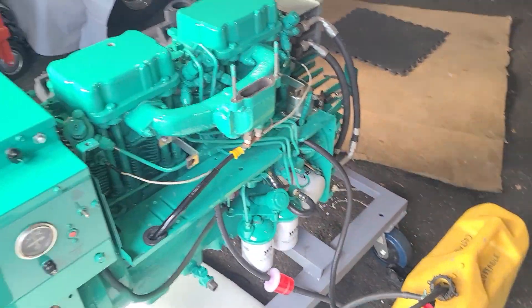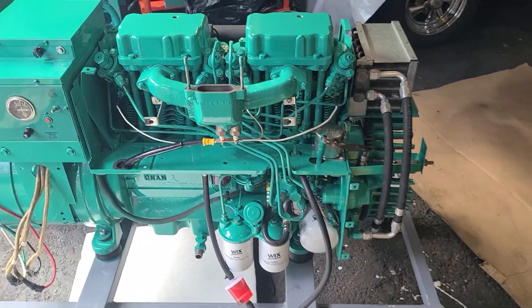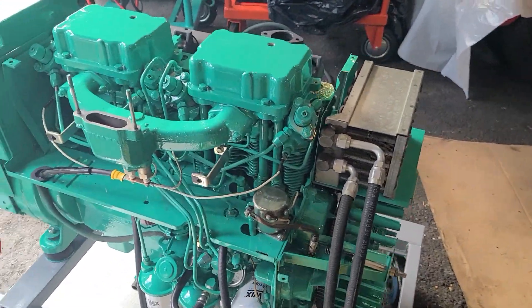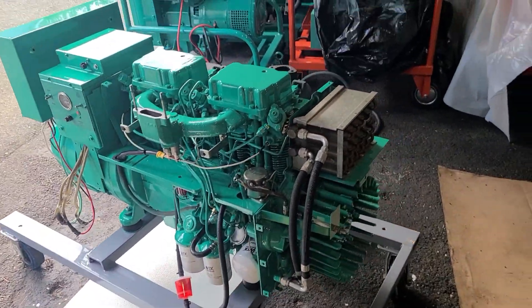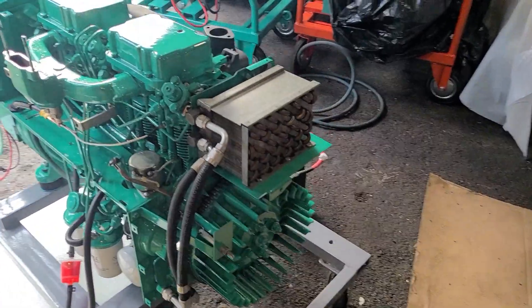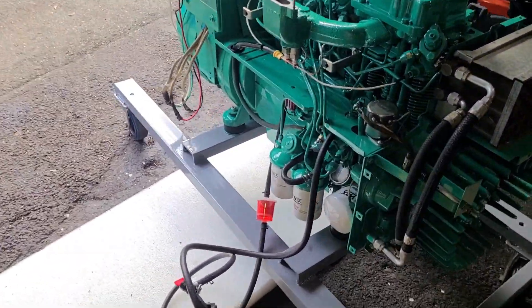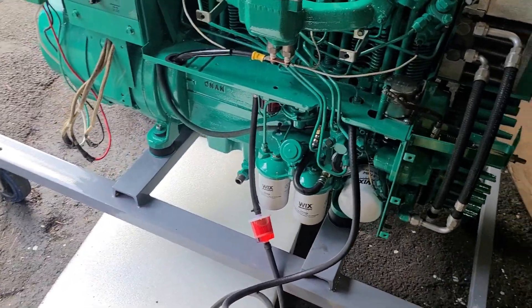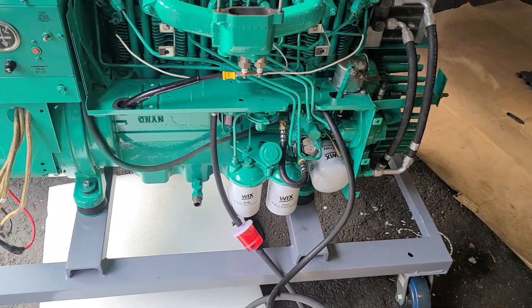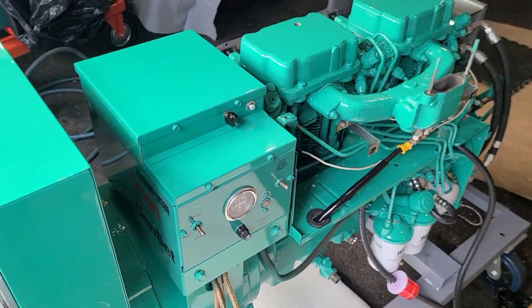This was the first fire-up of the 15.0 DJC after the rebuild, and we got a lot of smoke in here. We don't have the cooling tins on, so we don't want to run this thing too long. But it started right up after I bled it — that's the fuel — and we got some oil going, got excellent oil pressure. Glow plugs and everything work great.